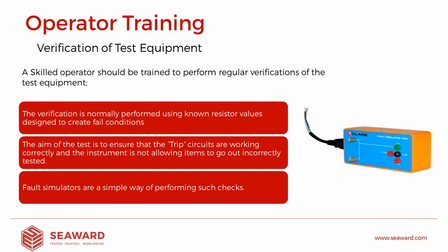So on a regular basis, it's definitely recommended that a skilled operator is able to perform these kind of verification checks. Now, to make things nice and simple for you all, Seaward have a range of fault simulators designed exactly for this task. So if you do want to pick this up and move it on a production line, we have a solution. We can very quickly offer that kind of simple verification check. It should take no longer than testing the very first product. So it should only really add a couple of seconds onto your day from a production point of view.